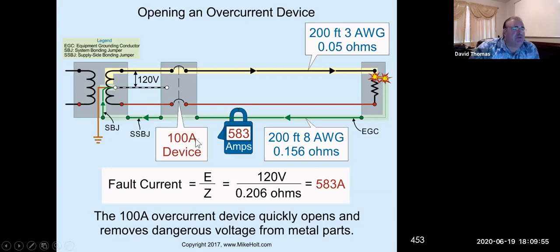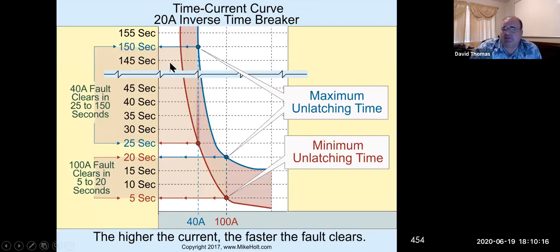So just so you know, that's about 500%, and that's typically what we use for our calculations: 500% of the breaker setting, as in the amount of current that we expect in our circuits. Okay, but our breaker will trip hopefully real quick, depending on what type of breaker we have.